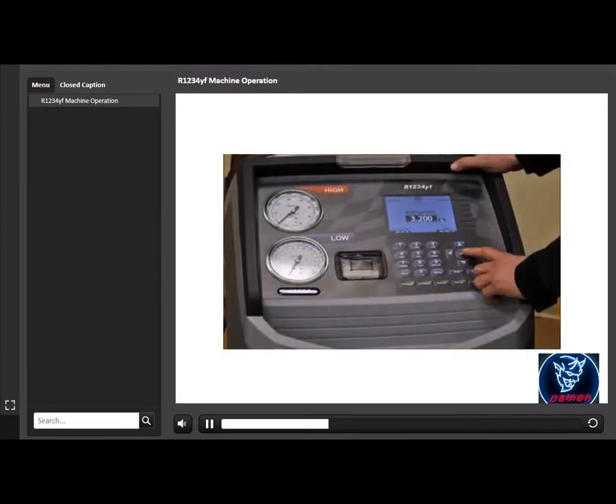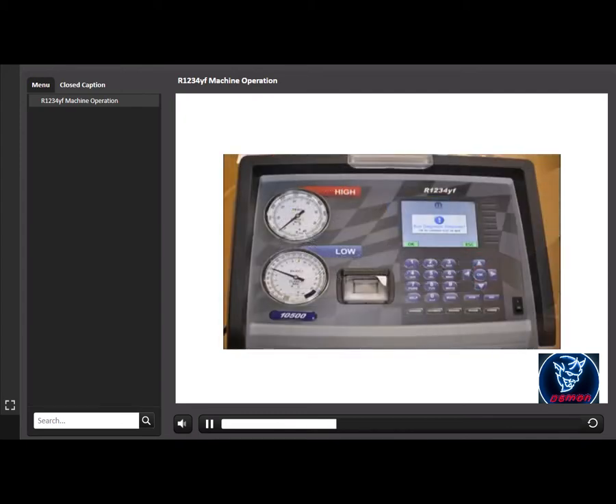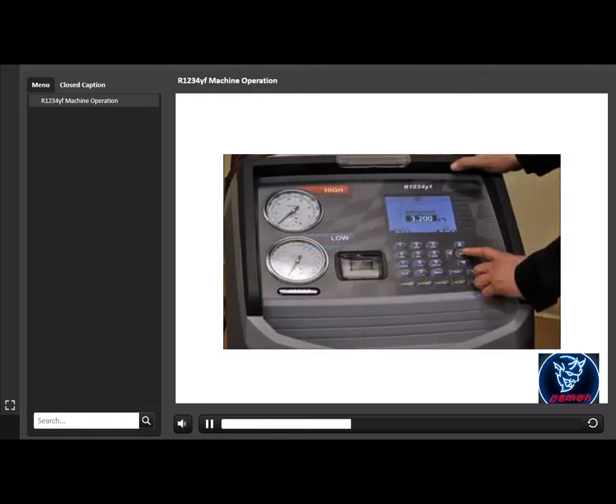If no pressure is detected, the machine proceeds to the next programmed mode, vacuum or charge. If pressure is detected, the machine prompts to run diagnostic pressures before recovery. Running diagnostic pressures before recovery is optional. Diagnostic pressures should be run when prompted after a charge. Press OK to run diagnostic pressures, or press Escape to continue with recovery.